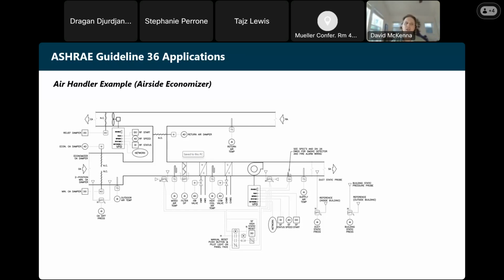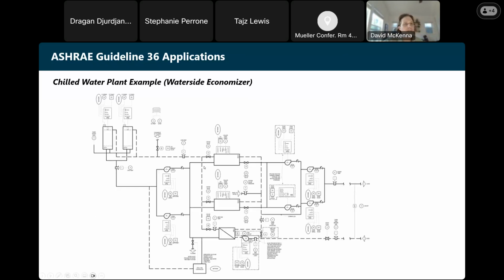So again, enormous energy savings there that I think, when you marry the software and the hardware side, you can see hopefully quite clearly how this serves to save energy. So again, one example of this is the air side economizer. The other one that we'll look at briefly is the water side economizer, which is a very similar system. What we're looking at here is a chilled water plant schematic of a controls diagram. So in this particular case, we have two water-cooled chillers, two cooling towers, primary pumps, secondary pumps, condenser water pumps. So it's a pretty typical setup for what we see.